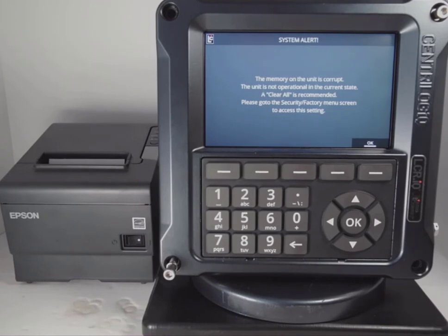As part of this instruction, since we're going from an older version of software to this newer version, it's telling me there's a system alert and a corrupt file in the memory. This is normal and typical when upgrading from version 108 to version 111. It means not all the files line up exactly correctly, so the best thing to do is perform a clear all, as it's recommending on the screen.